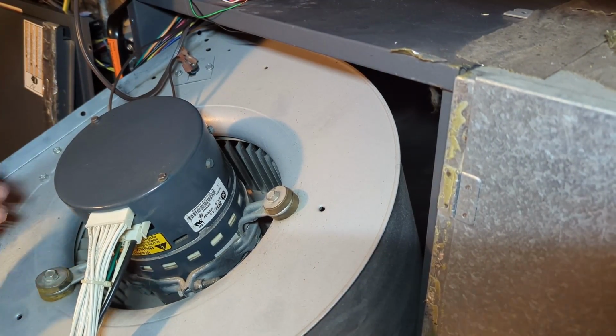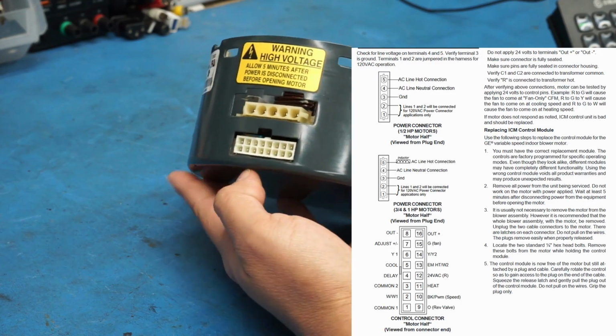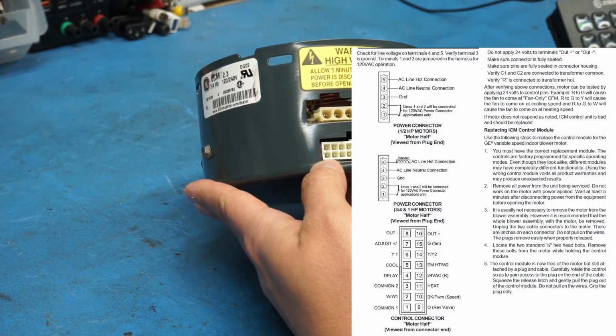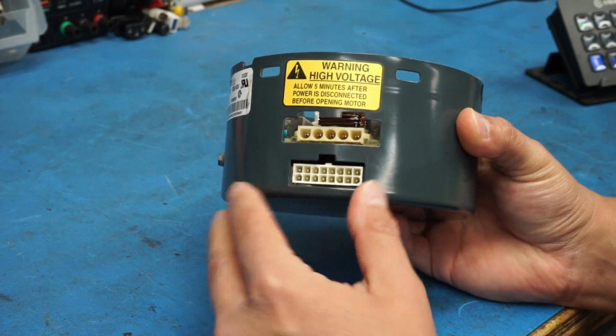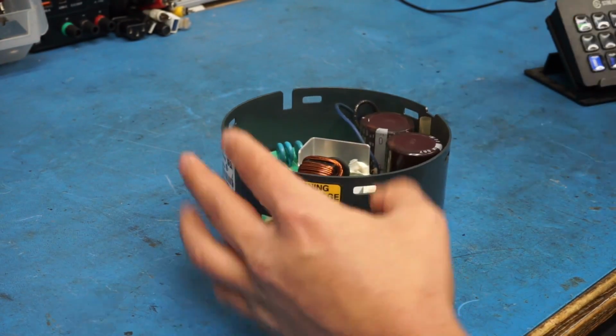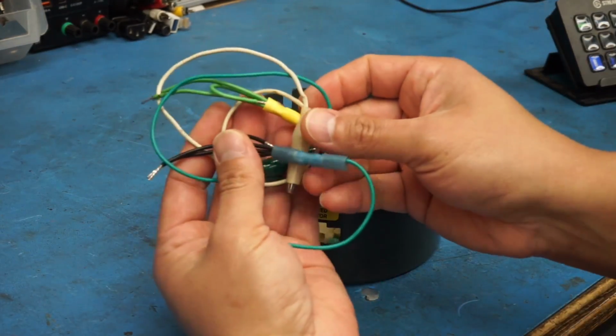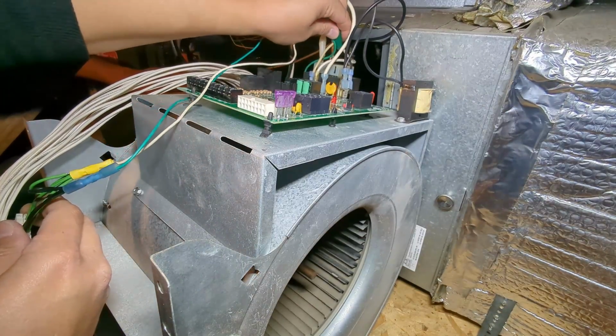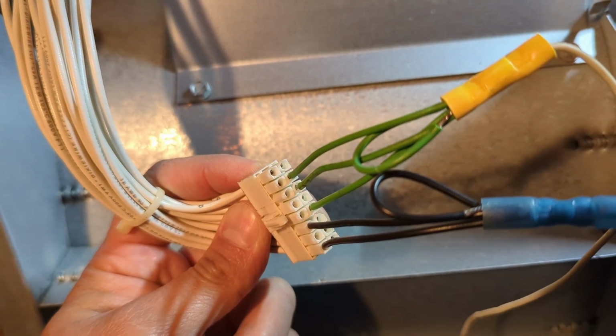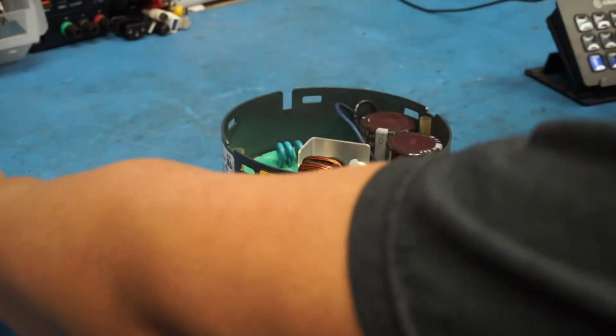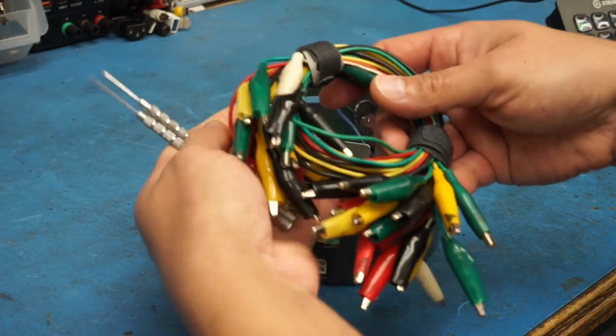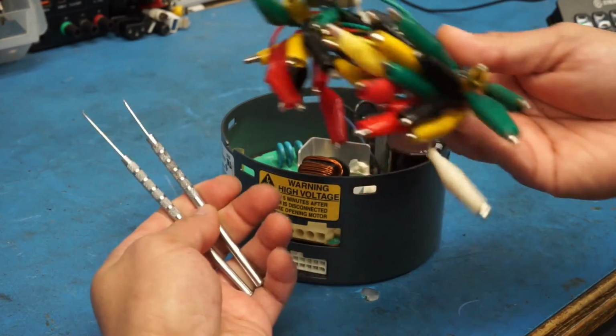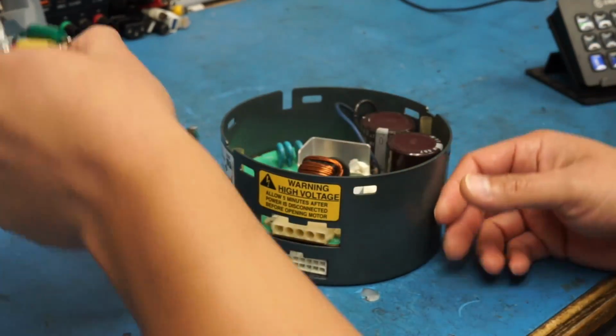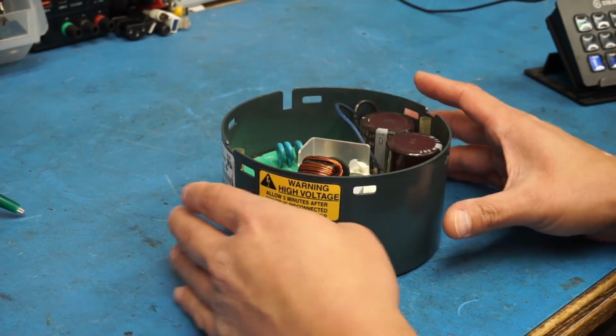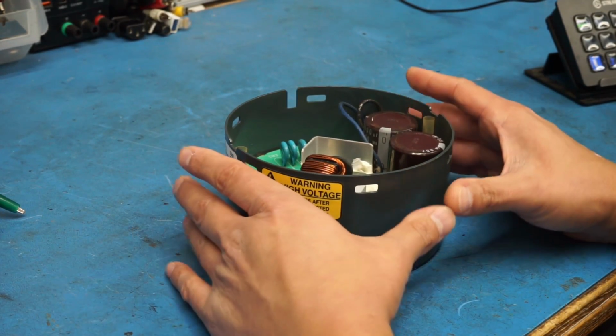I found some information online on how to test these, and it turns out they can be pretty easily tested by applying like 24 volts AC to some of the pins on the control header, which is this 16-pin connector right here. So I made these test leads to make it easier to test, and I used the transformer on the unit itself to apply power to the pins. But I didn't have this made when I initially tested the controller, so I had to manually jump some of this stuff on the board with picks and alligator clips. But it was enough to rule out any issues with the control board inside the furnace.